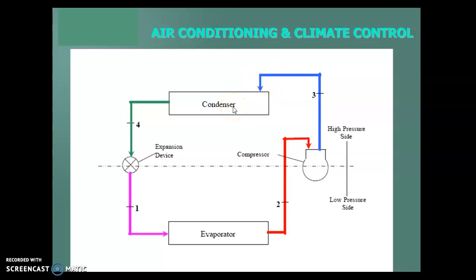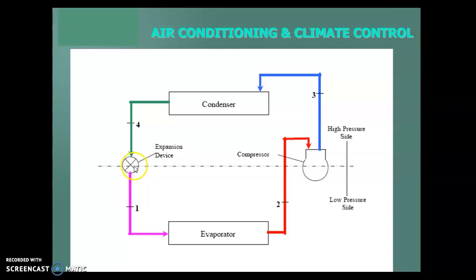When it gets to the condenser, it has atmospheric air and a fan blowing on it. By name, it's going to condense into a liquid. When it does that, it rejects the heat in the refrigerant — this high-pressure, high-temperature gas turns into a high-pressure, high-temperature mostly liquid over here. As it comes out of this liquid state, it goes to an expansion device and then divides to the low side, going through a fixed orifice or thermal expansion valve, where it becomes a low-pressure, warm liquid.